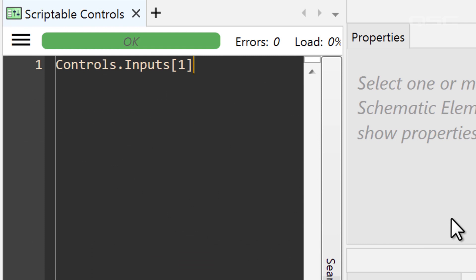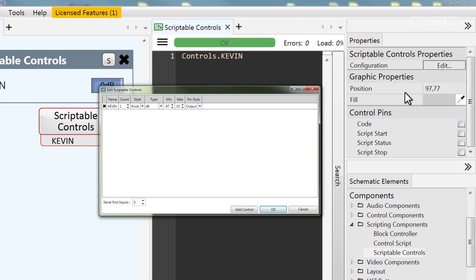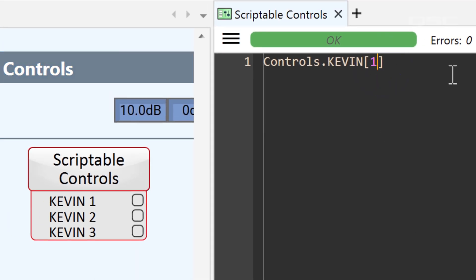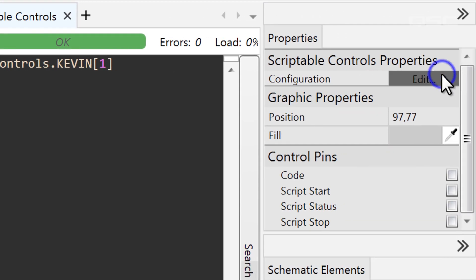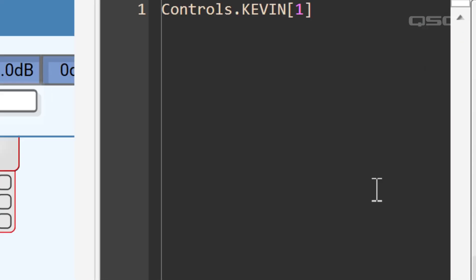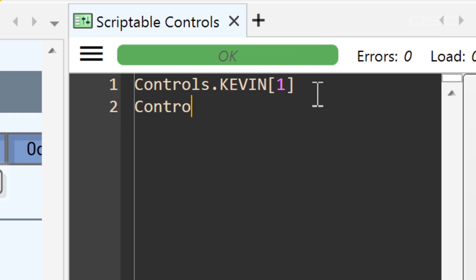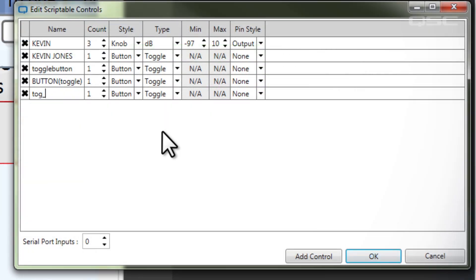Rather than controls.inputs[1] as seen in the previous example, you can now reference a named control directly with controls.kevin in the script. If you add multiple counts to the same control, you'll have to reference that index in the Lua control tree like this: controls.kevin[1]. Be careful about using spaces in the names of your controls — if your control name includes a space, you'll need to reference it in brackets and quotes, like controls["kevin jones"]. Also, do yourself a favor and use a consistent naming convention so that if another programmer needs to work on this design someday, they can easily understand your labels.